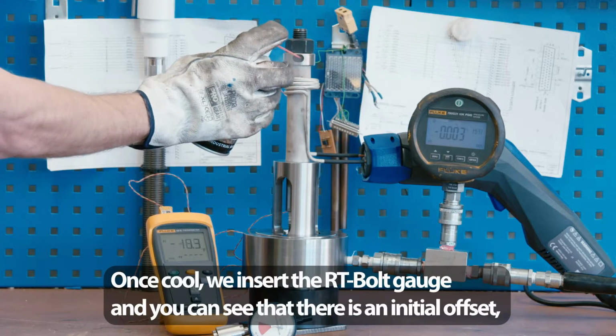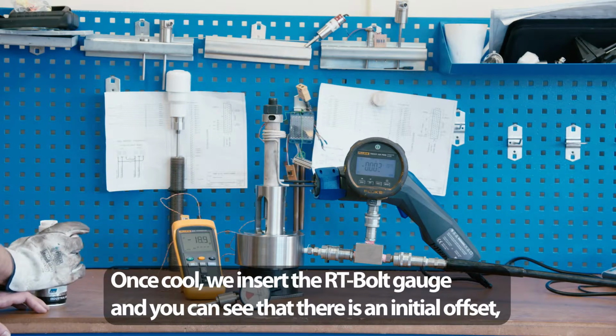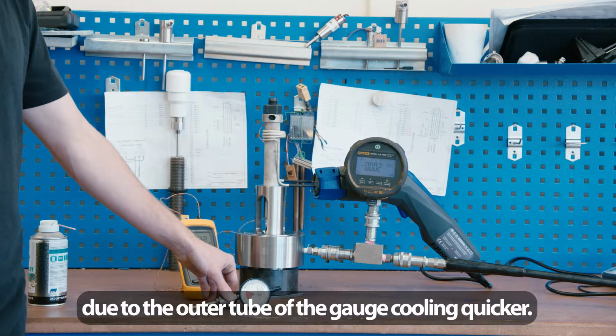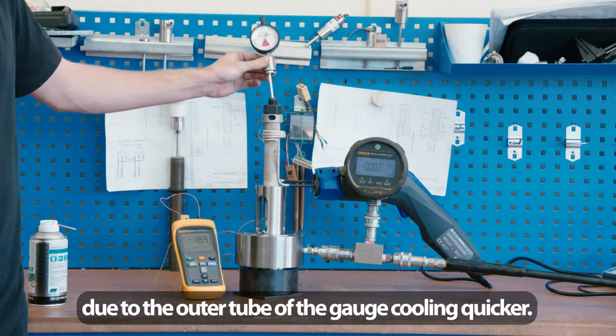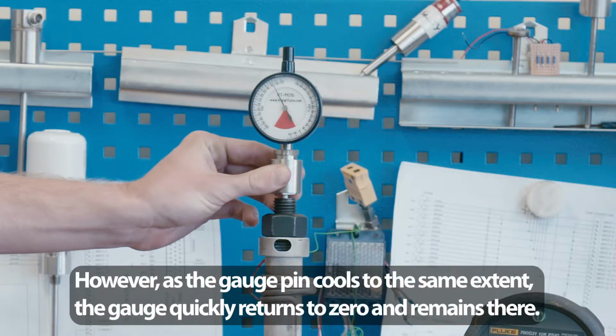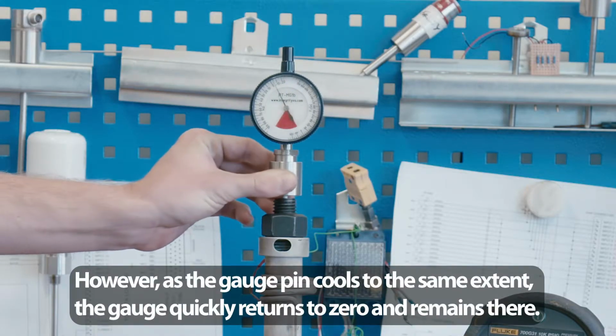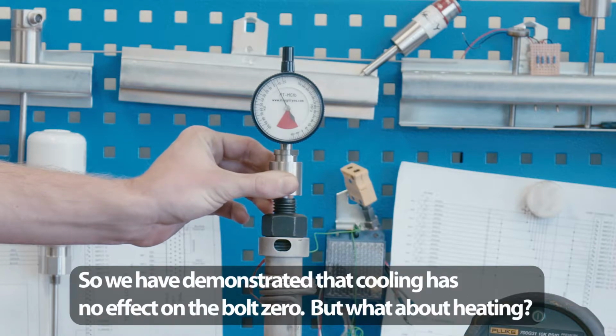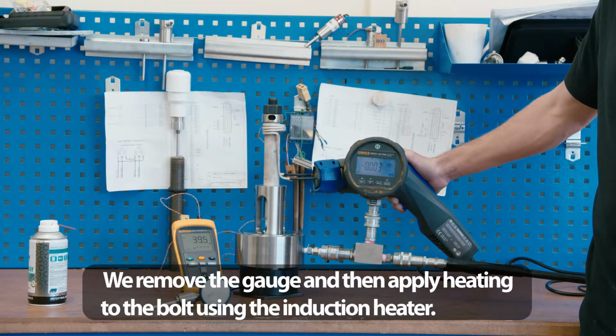Once cool, we insert the RT bolt gauge, and you can see that there is an initial offset due to the outer tube of the gauge cooling quicker. However, as the gauge pin cools to the same extent, the gauge quickly returns to 0 and remains there. So we have demonstrated that cooling has no effect on the bolt 0. But what about heating? We remove the gauge and then apply heating to the bolt using the induction heater.